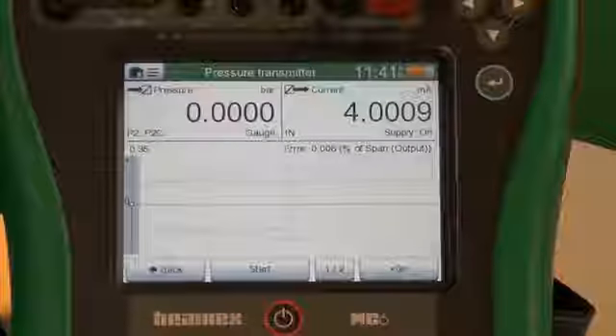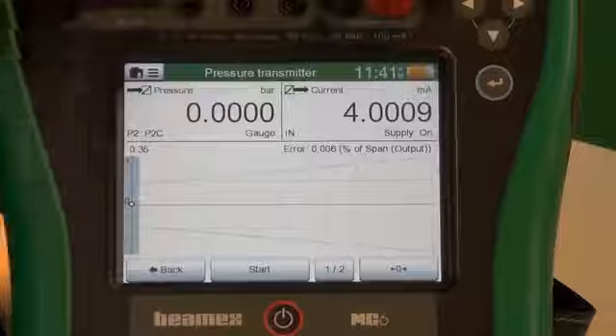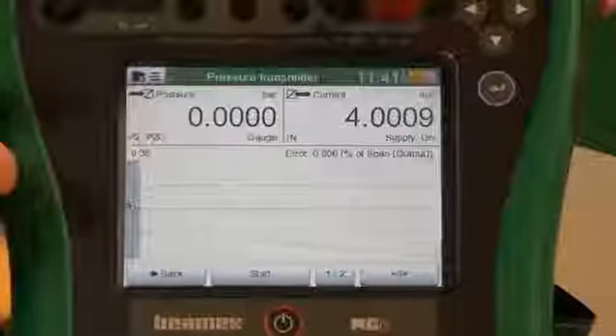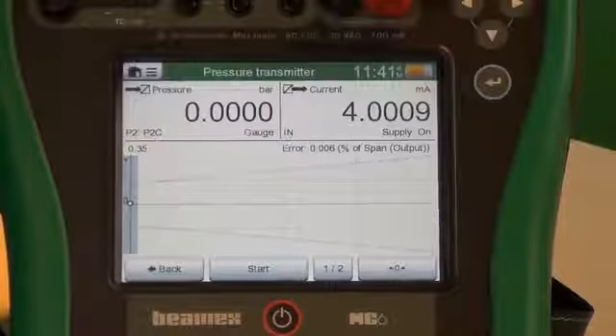At the bottom you've got the error limit and error graphics. You can see them widening, because we've used a combination of percentage of span and percentage of reading. You can also see that we are on the first instrument out of two in this group.